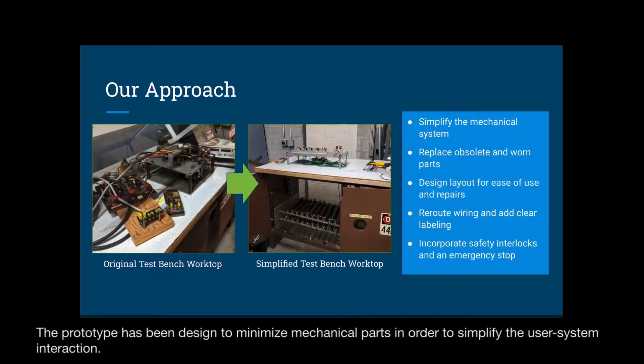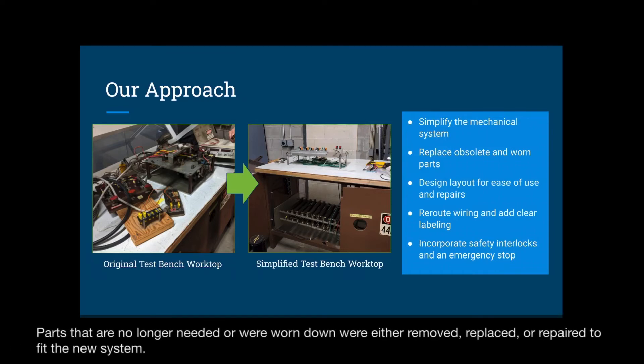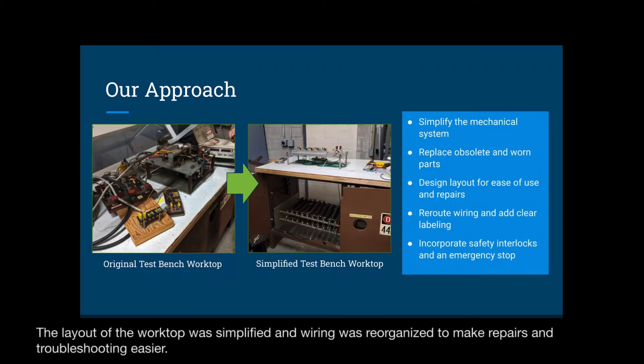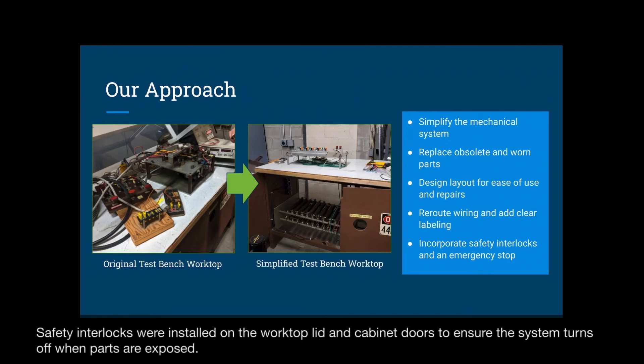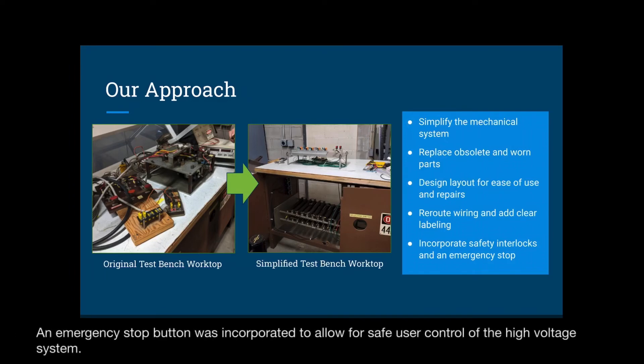The prototype has been designed to minimize mechanical parts in order to simplify the user-system interaction. The parts that are no longer needed or were worn down were either removed, replaced, or repaired to fit the new system. The layout of the worktop was simplified and wiring was reorganized to make repairs and troubleshooting easier. Safety interlocks were installed on the worktop lid and cabinet doors to ensure the system turns off when parts are exposed. An emergency stop button was incorporated to allow for safe user control of the high voltage system.